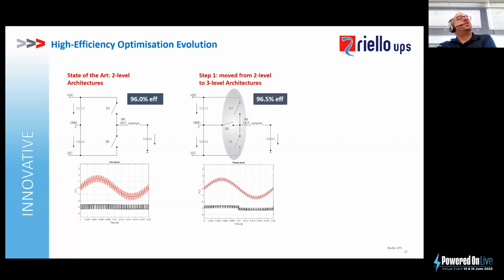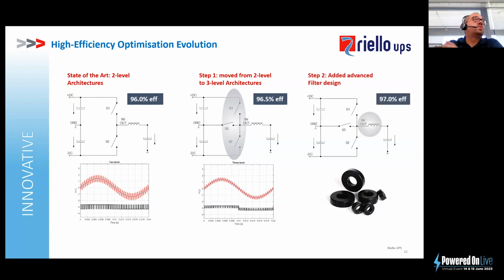We then made the step of moving away from the two-level architecture across to the three-level architecture. Now, the three-level architecture obviously requires more components and more processing power to control. So typically, when these were first introduced, you would only really see three-level architecture in large UPS systems, 100, 200, 300 kVA plus, because of the complexity, the number of components, and the overall cost. It was not cost effective to produce UPSs with this architecture. However, nowadays, because technology has moved on, you will see the three-level architecture in UPSs as small as 10 kVA.